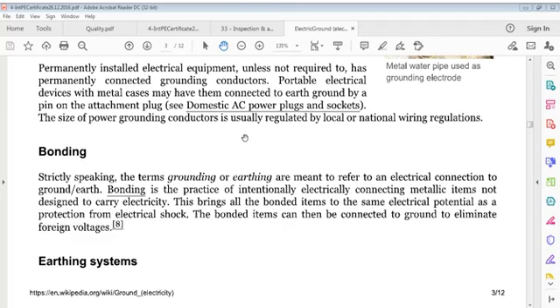Bonding. Strictly speaking, the terms grounding or earthing are meant to refer to an electrical connection to ground or earth. Bonding is the practice of intentionally electrically connecting metal items not designed to carry electricity. This brings all bonded items to the same electrical potential as protection from electrical shock. Bonded items can then be connected to ground to eliminate foreign voltage.